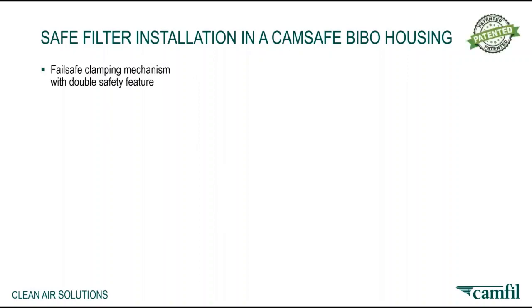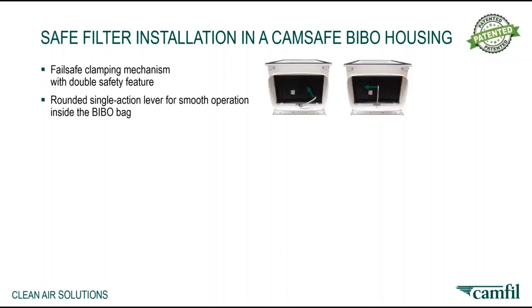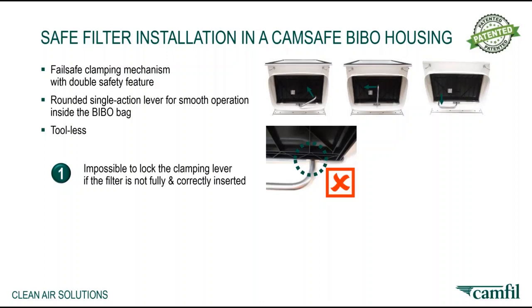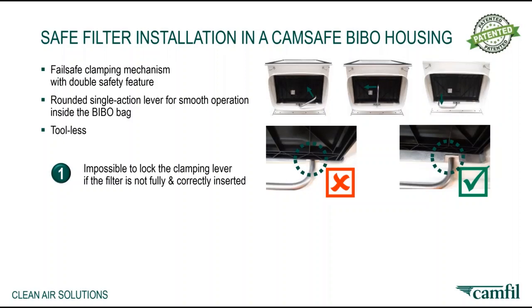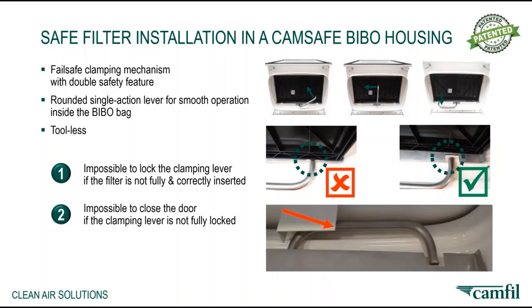In this example, we see the CamSafe BIBO housing with its fail-safe clamping mechanism, including a double safety feature. It uses a rounded single action lever. The roundedness is for smooth operation inside the bag, and it's of course completely toolless. But what's important, it is strictly impossible to lock or even move the clamping lever if the filter is not correctly inserted. And then it is impossible to close the door if the clamping lever is not in the fully locked position.